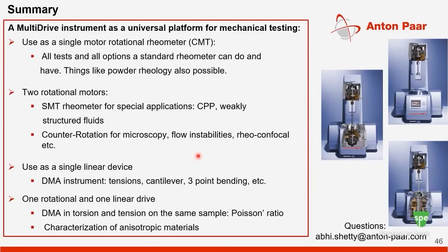How high in temperature can the DMA device handle in axial mode? The stuff I showed today is mostly with the CTD 600, which goes up to 600 degrees, but we have capability to go much higher. We have a multi-drive device that goes up to 1000 degrees, so you can do axial measurements like three-point bend type measurements up to about 950 to 980 degrees, close to 1000 degrees.